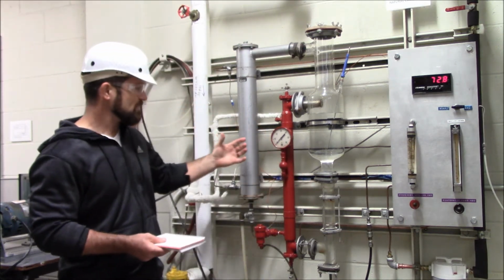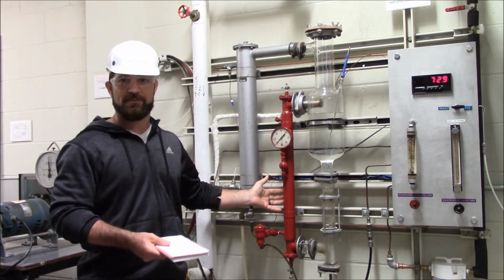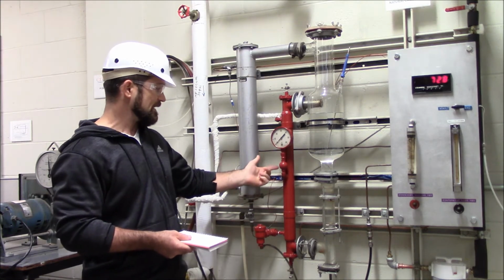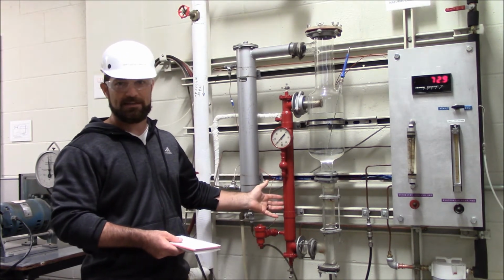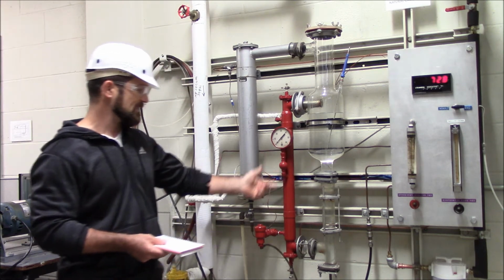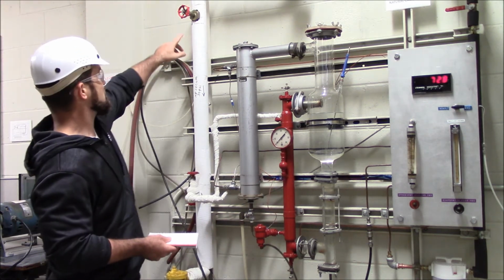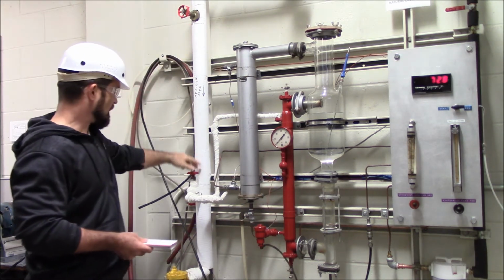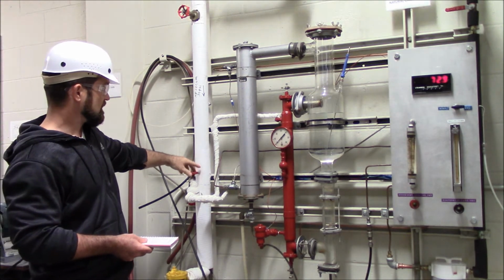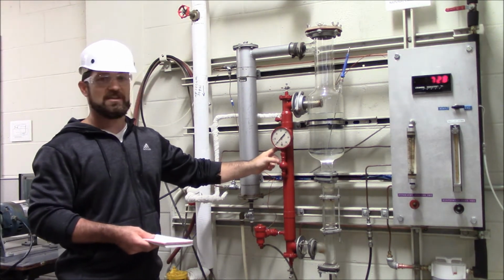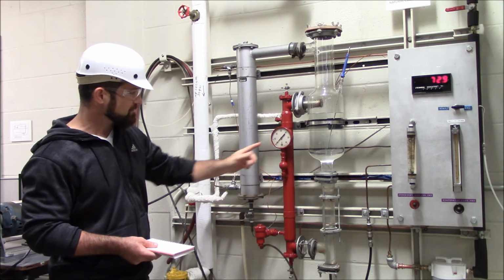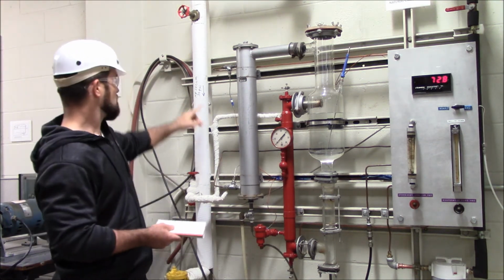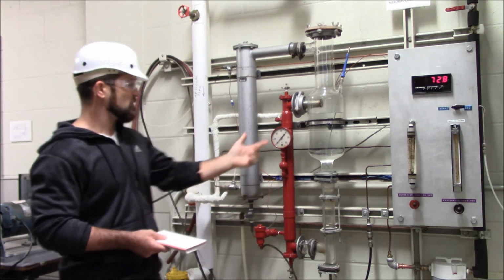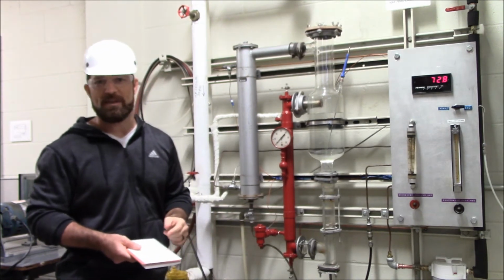Okay, so with that set, to do the evaporation we need heat. We can get that heat by supplying steam to the heat exchanger. The main supply line for the steam is shown here. There's another valve to control the steam flow or the steam pressure to the evaporator. The maximum pressure you're going to be able to get on this system, because it's medium pressure steam, is about 30, maybe 32 psi.